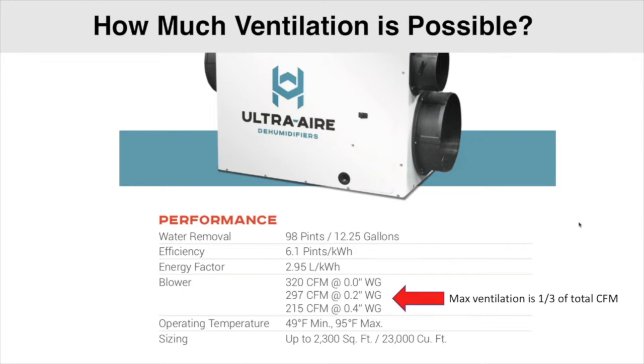So here is our spec sheet, and this is for the Ultra Aire 98. If we look at the column there with all the different listed CFMs, we have 320 with no static on that system, 297 CFM with 0.2 inches of water column, and then we're at 215. So it's important that we know what our static pressures are on that system in order to figure out the max, again, that we're going to be able to get through that dehumidifier.